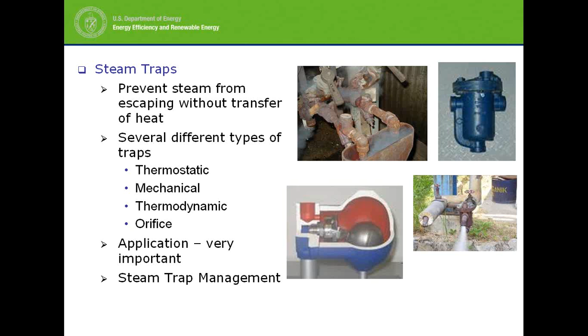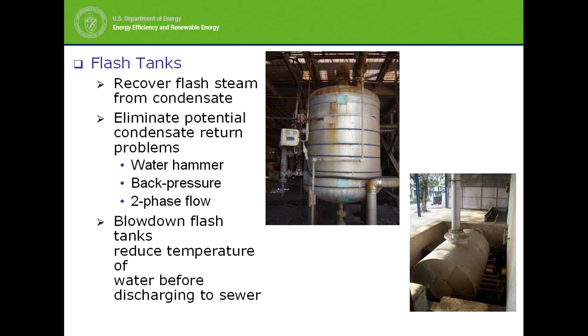A lot of places have flash tanks. Flash tanks serve a huge number of purposes. First and foremost, they're great sources of recovering energy from condensate - high pressure condensate flashing to low pressure steam. They also often improve system reliability significantly, eliminating problems like water hammer, back pressure, and two-phase flows. Recovery of energy is key, but ensuring the system operates reliably is very important from a plant perspective.